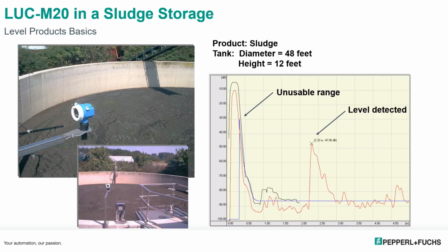This is an example of a sludge storage facility, a cement tank, and they have the probes stuck on the end of a bracketing that they made. And you can see the chart off to the right. That unusable range is basically your blocking distance where it can't be used. However, you can see the signal running through the air, bouncing off the medium and coming back. And you can see where it's detecting it around 2.4 meters and gives a pretty good dB signal back as an indication of where the medium is.